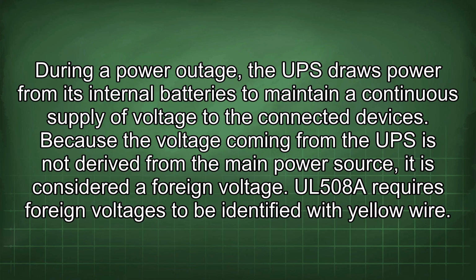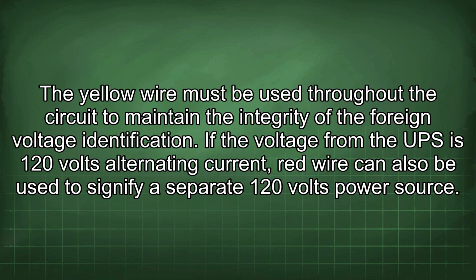UL508A requires foreign voltages to be identified with yellow wire. The yellow wire must be used throughout the circuit to maintain the integrity of the foreign voltage identification. If the voltage from the UPS is 120 volts alternating current, red wire can also be used to signify a separate 120 volts power source.